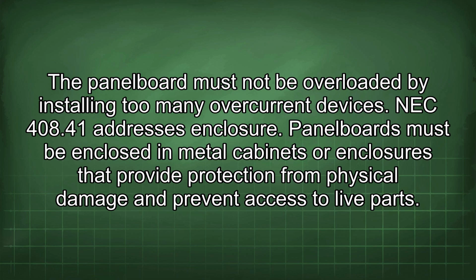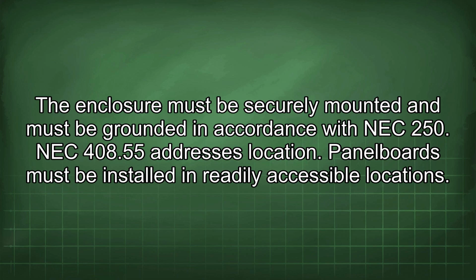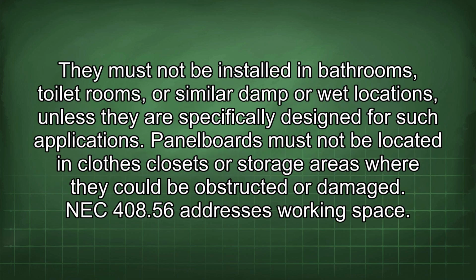NEC 408.41 addresses enclosure. Panel boards must be enclosed in metal cabinets or enclosures that provide protection from physical damage and prevent access to live parts. The enclosure must be securely mounted and must be grounded in accordance with NEC 250. NEC 408.55 addresses location. Panel boards must be installed in readily accessible locations. They must not be installed in bathrooms, toilet rooms, or similar damp or wet locations unless they are specifically designed for such applications. Panel boards must not be located in clothes closets or storage areas where they could be obstructed or damaged.